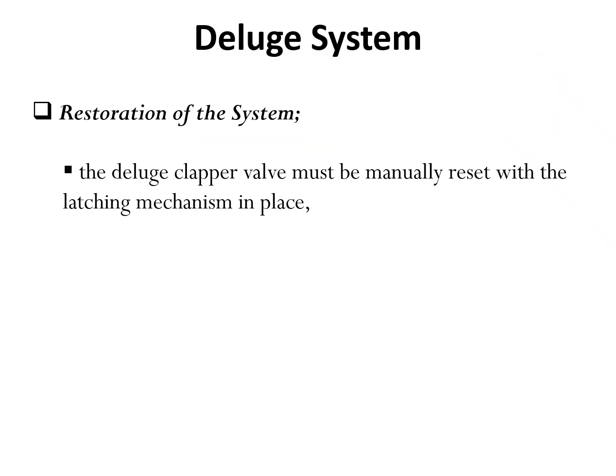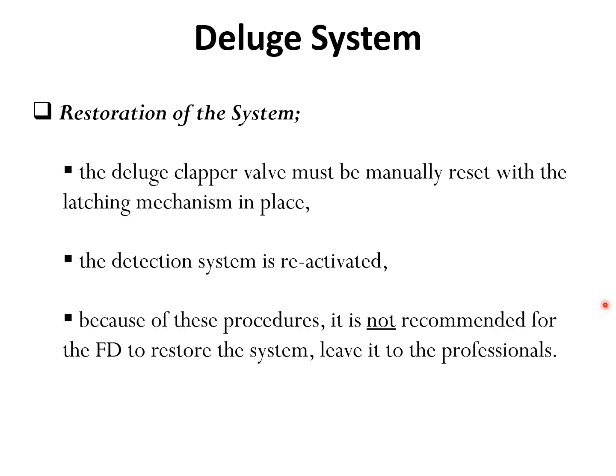Friends, this particular slide shows how to restore the system after operation. The deluge clapper valve must be manually reset with the latching mechanism in place. The detection system is reactivated. Because of this procedure, it is not recommended for the FD to restore the system. Fire department, FD means, leave it to professionals.